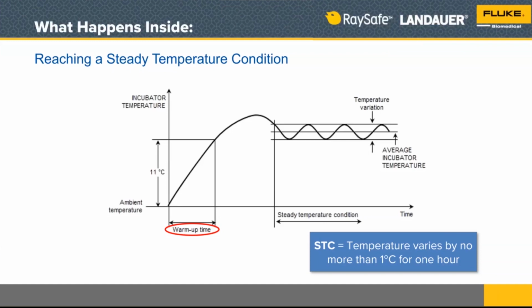So we're going to measure that, and then we're going to take a look at the overshoot. As this heater element heats up, it can overshoot our actual temperature set point. So it may go a little bit above that, but we don't ever want it to go more than 2 degrees C over our temperature set point. We're going to look for that at the appropriate time and make sure that it begins to stabilize and doesn't ever overshoot more than that 2 degrees C. And this is during this 1 hour of testing that we're going to do, or a little bit more. And then we're going to look for any undershoot as well. What we want is to see that the stable state and the temperature control is going to stay within the specification boundaries that the manufacturer gives us.